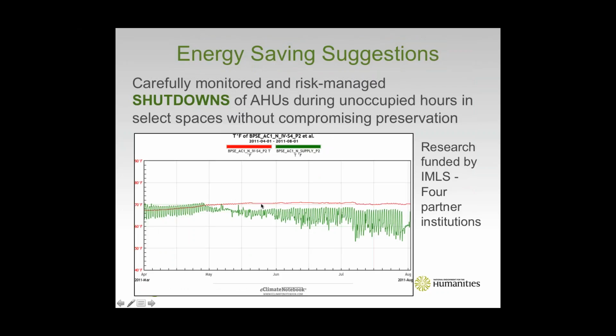This is one particular example. And when we're looking at this situation, these spikes or these fluctuations in the green line, which is the supply air condition, show the shutdown occurring, right? We have day and night conditions in the supply air. But as we look at the space condition in this particular circumstance, there's very little fluctuation as a result of this shutdown. You see maybe not even a half degree as a result of that.